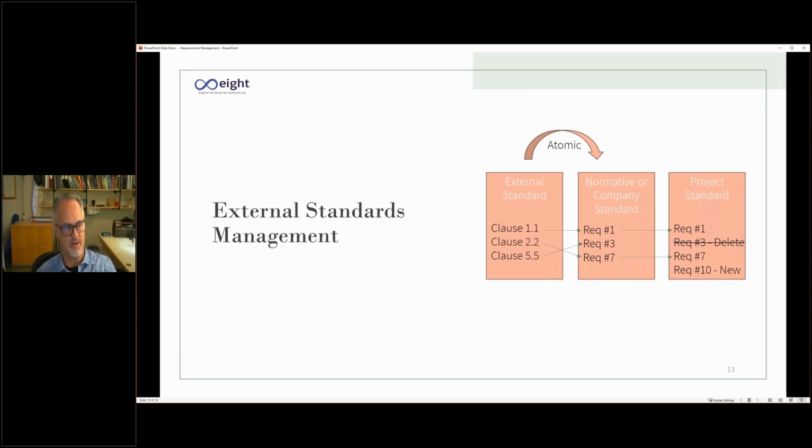So now we have this understanding for this product type, how we're going to satisfy all of these external standards. And there might be, I mean, the last product I did, I think we had 35 standards we had to be compliant with. It's not uncommon to have several hundred, especially when you start talking about complex medical devices where you have software and hardware and all the different disposable devices, all that. So very common that we have many standards that we're trying to be compliant with.